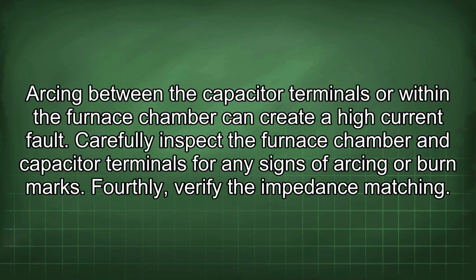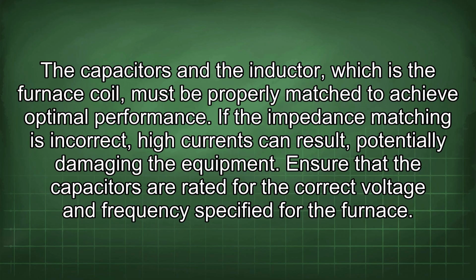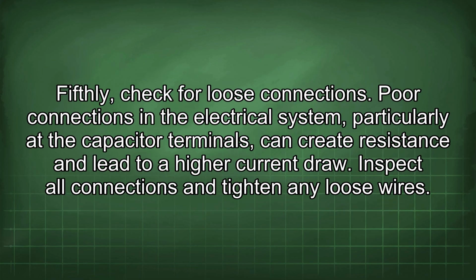Fourthly, verify the impedance matching. The capacitors and the inductor, which is the furnace coil, must be properly matched to achieve optimal performance. If the impedance matching is incorrect, high currents can result, potentially damaging the equipment. Ensure that the capacitors are rated for the correct voltage and frequency specified for the furnace. Fifthly, check for loose connections. Poor connections in the electrical system, particularly at the capacitor terminals, can create resistance and lead to a high current draw. Inspect all connections and tighten any loose wires.